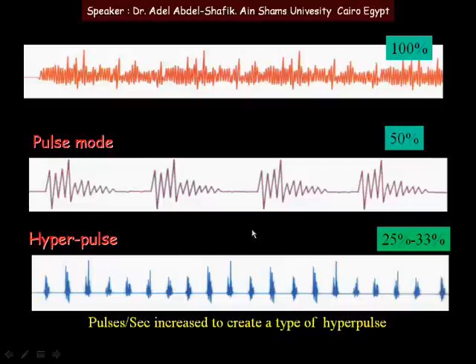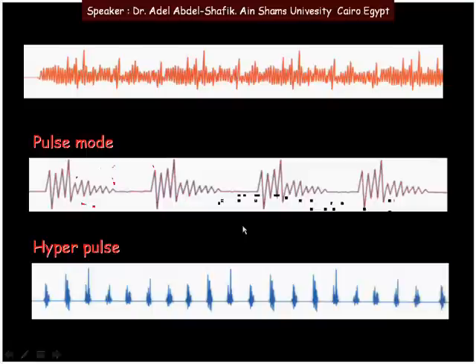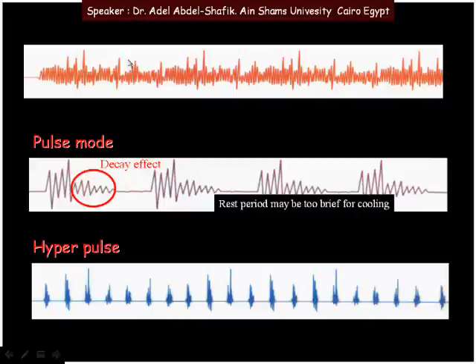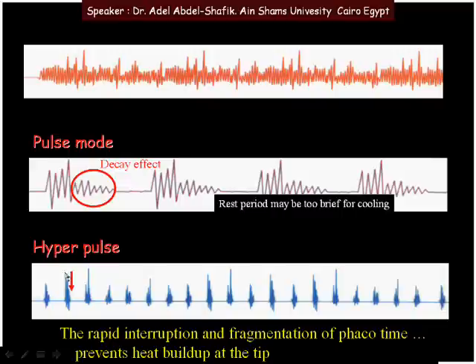This gives a total reduction in the amount of ultrasound delivered. With continuous ultrasound, heat builds up significantly. With regular pulses, there is some time for cooling, but the decay of the pulse is gradual, so there may not be enough cooling time. In hyper pulse mode, there is an abrupt end to each pulse and enough time for cooling, which prevents heat from building up at the tip. Because there is no heat buildup, we can use the tip needle without a sleeve, allowing smaller incisions and ultimately less astigmatism.